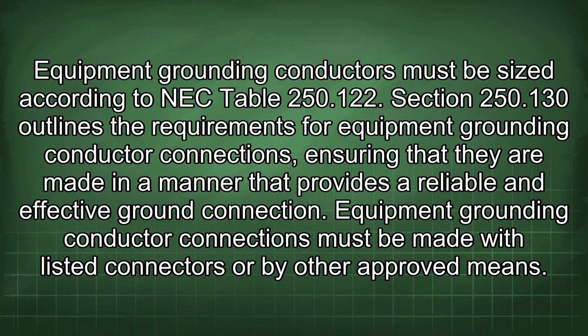Section 250.130 outlines the requirements for equipment grounding conductor connections, ensuring that they are made in a manner that provides a reliable and effective ground connection. Equipment grounding conductor connections must be made with listed connectors or by other approved means.